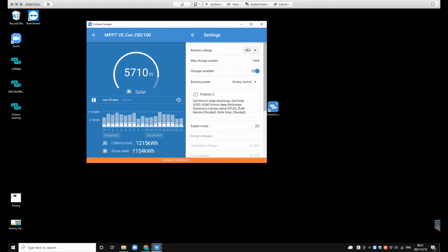Obviously we are running a 48-volt system. If it's not selected, please select it as 48 volts. You want user-defined settings, and your max charge current in most settings you can basically leave at maximum of what the MPPT is capable of.